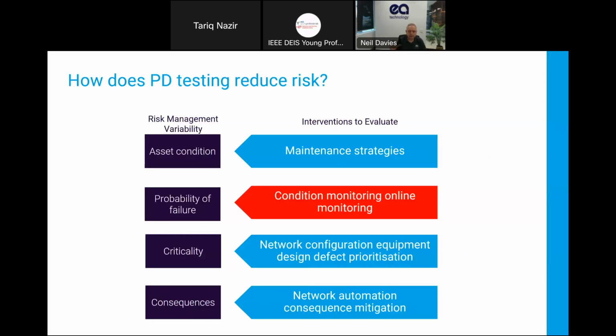So where does partial discharge and condition monitoring play in that reduction of risk? Well, it's not changing the asset condition. So in order to change the asset condition and reduce risk, you need to maintain. But where it's really playing in this is it's reducing the probability of failure. So condition monitoring, online monitoring, will, if you act and intervene, reduce that probability of failure. If you're not going to act, you're not going to take heed of the data that's coming from your testing, then there's probably no point in doing it. But this is where we're doing it. So we're looking at reducing the probability of failure.